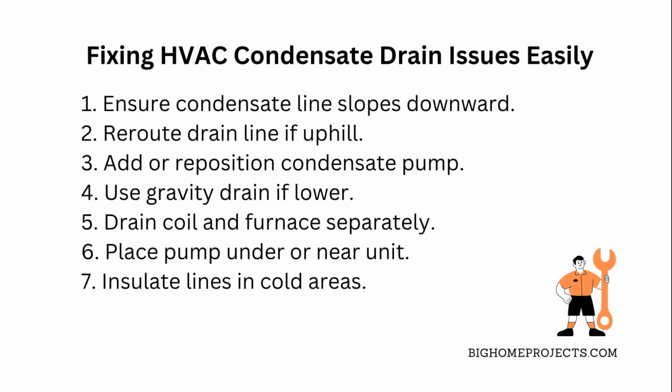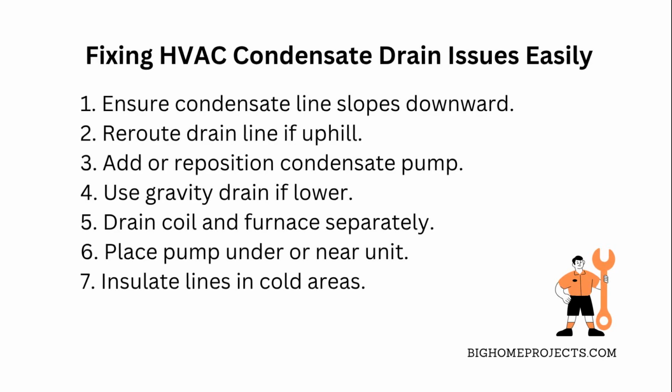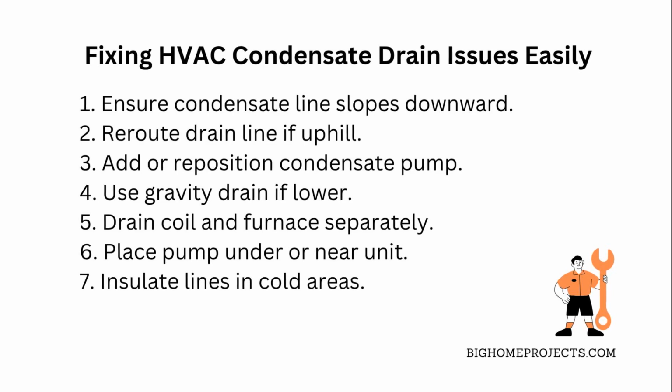Try rerouting the drain line so it naturally flows down to the pump without any uphill sections. If you can't adjust the pipe, adding a condensate pump with a lower inlet or repositioning the pump might help.